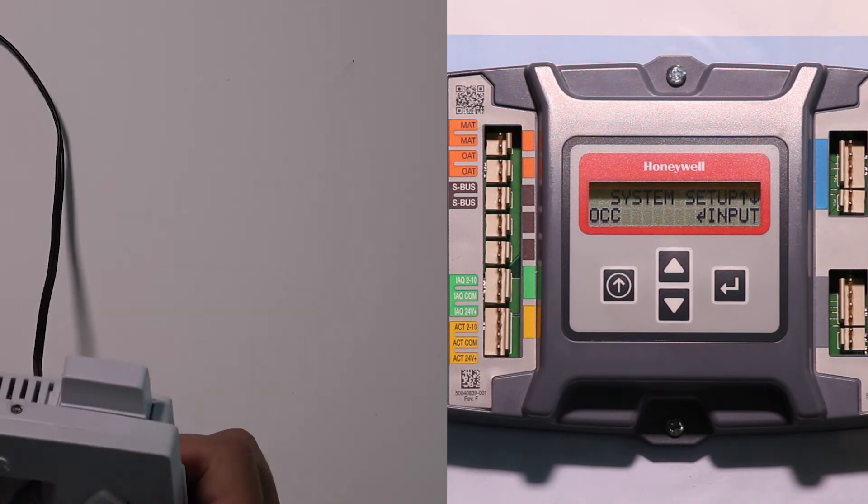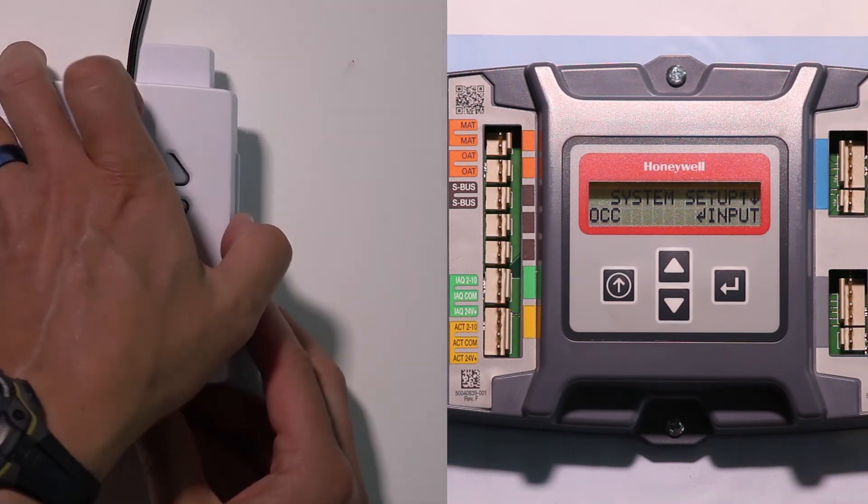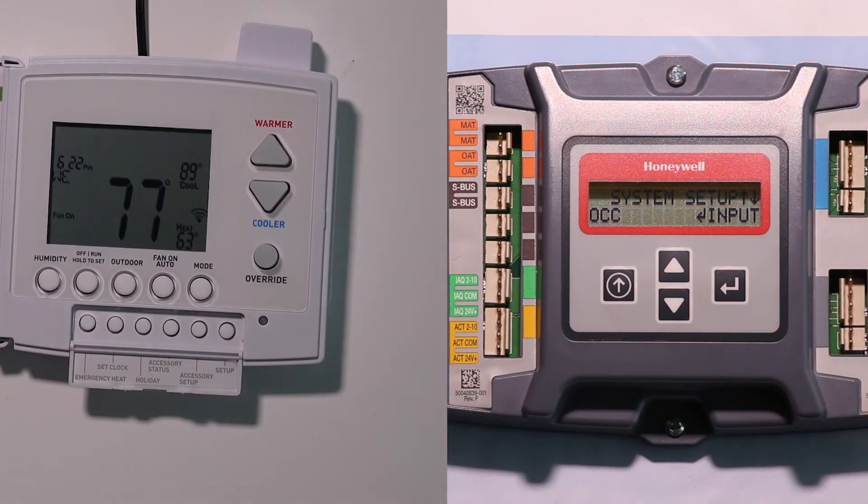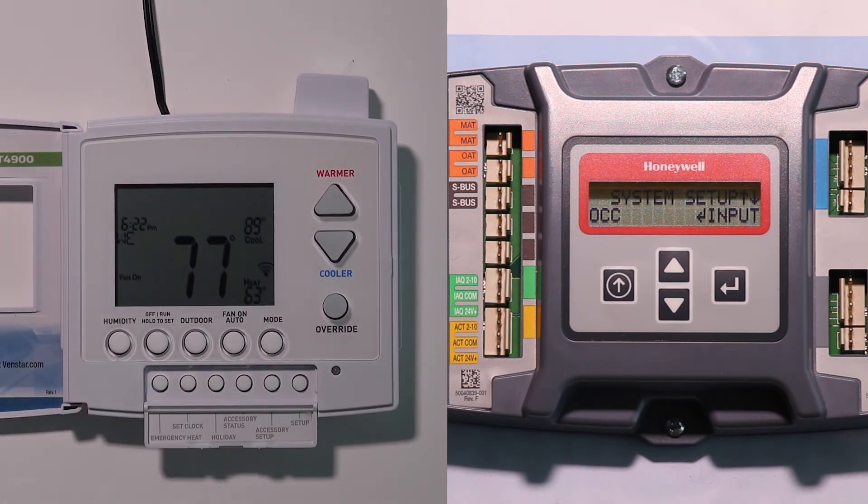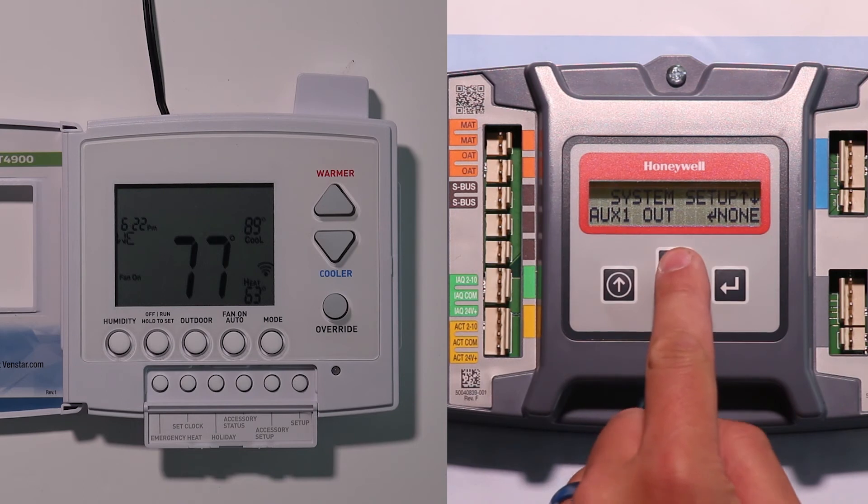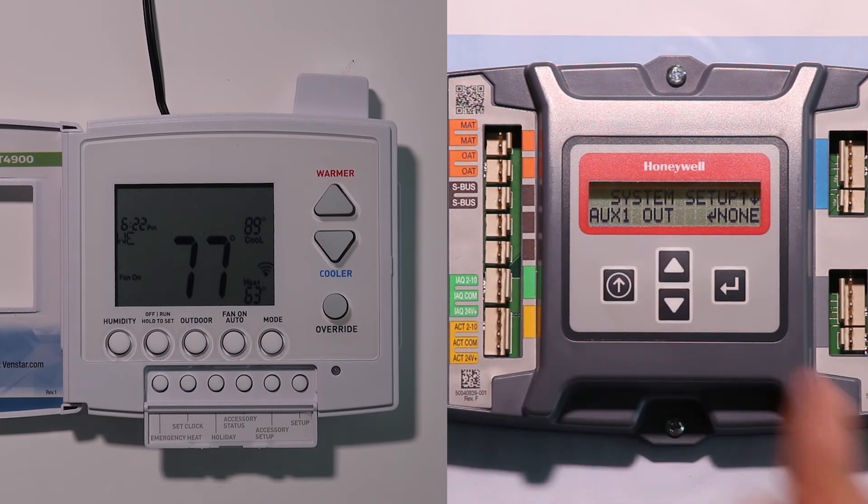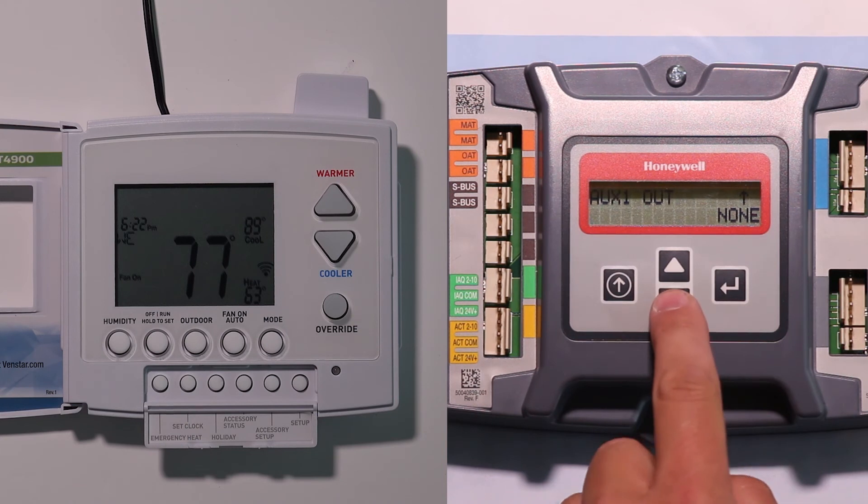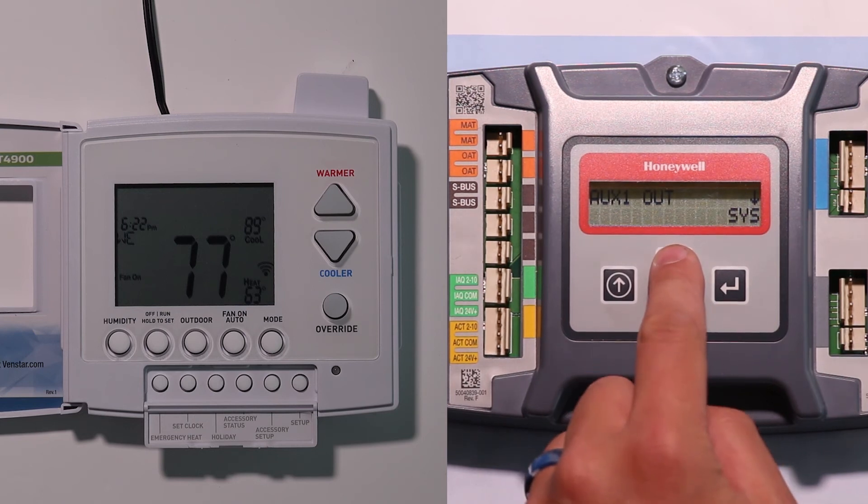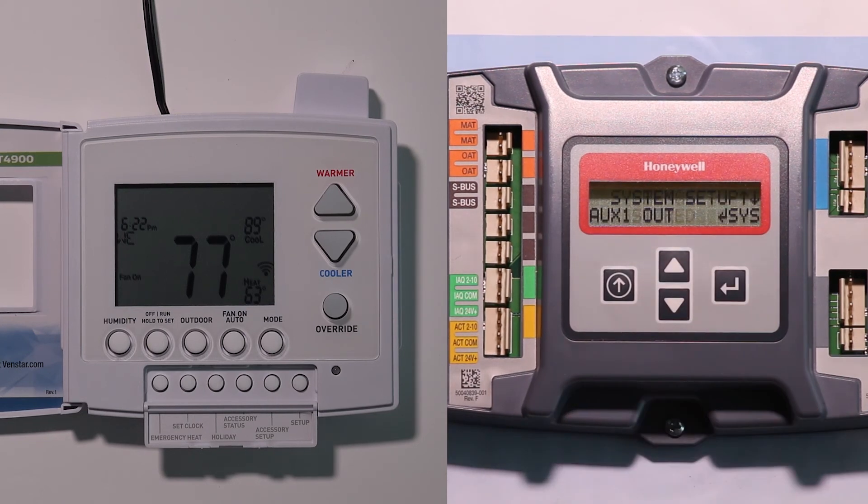So once we have these two guys wired with each other, we're going to configure them both again. So on our economizer controller, we're still under the system setup. If I go up one higher than the occupancy, I have the AUX 1 out. If I hit enter, I can change that. My choices here, as you will see, are ERV, exhaust, fan 2, or system. I'm going to pick system and save that. What that does is it sends out any system alarms from the economizer controller out on that AUX 1 output signal.